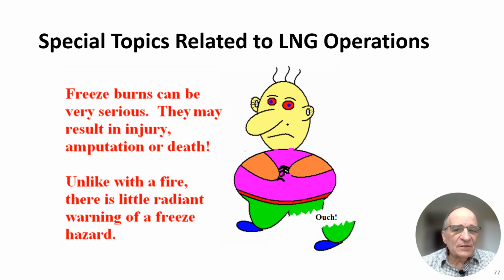Continuing on special topics related to LNG operations, realize that freeze burns can be very serious. They may result in injury, amputation, or death. And I know of at least one incident where the person died when a valve ruptured and he was covered with LNG. I experienced a freeze burn once on this finger, and I was making up a fitting. I had gloves on, and I was almost there, and I knew I was getting burned, but I said, "I got it," and I got the fitting, and then I took the glove off, looked at my finger, and it looked kind of strange, and it was burnt.